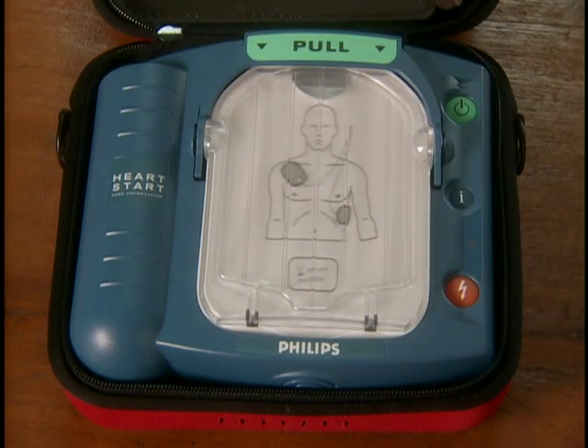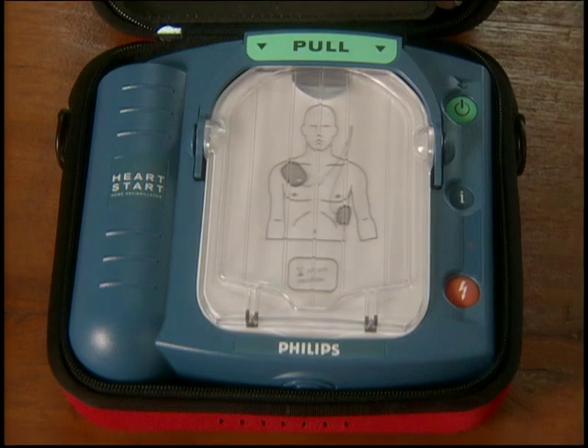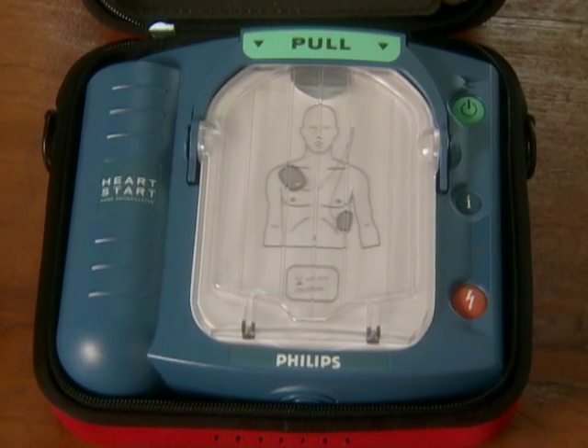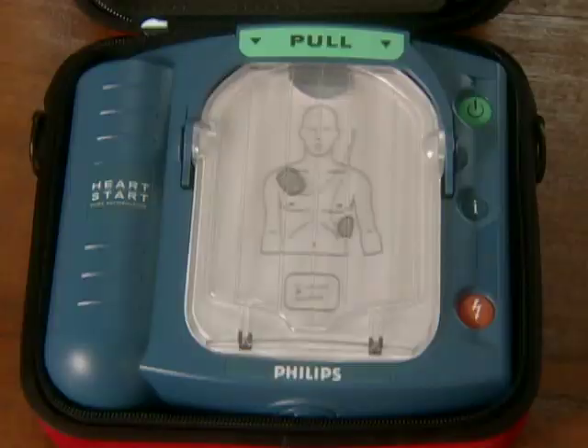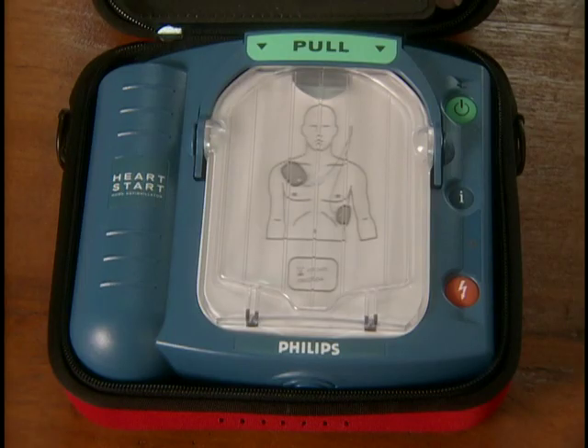The cartridge has a removable hard cover with a green handle. Underneath is a sealed package containing a pair of self-adhesive pads. Be sure you don't open the film seal of the cartridge until you actually need to use the pads. To work, the pads must have good contact with the patient's bare skin, and that is unlikely if the gel has dried out. And remember, always leave the hard cover in place to protect the pads until they're needed.